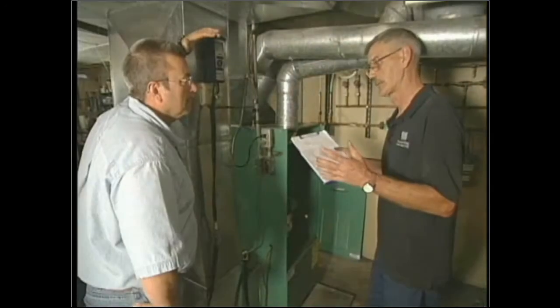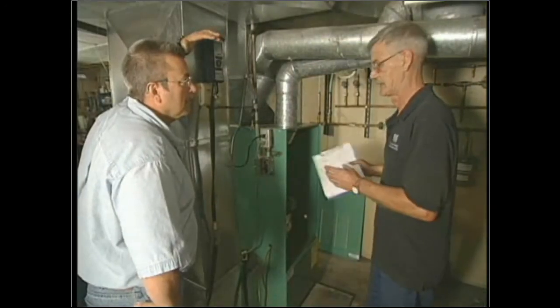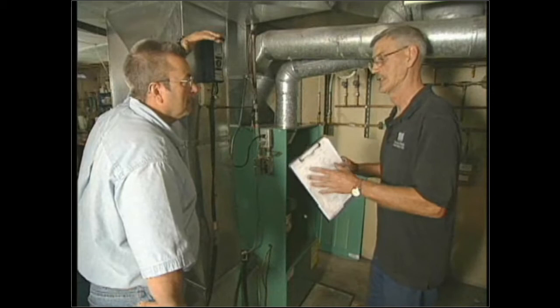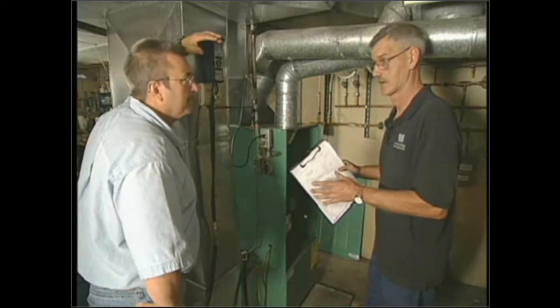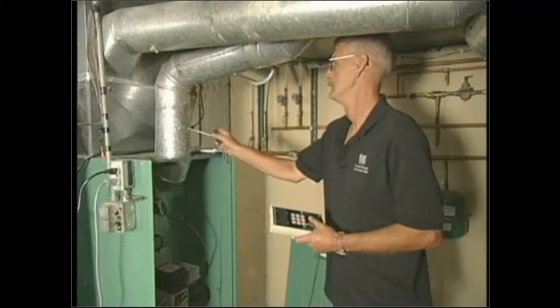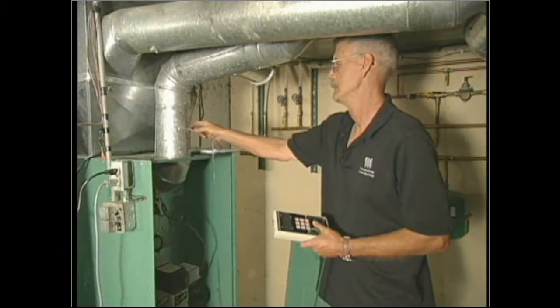If the pipe is too small, I can have spillage. If it's too large, then I don't get true draft if I'm measuring in the wrong spot. Okay. So I'll get it centered, then I'll take my reading, and that's all there is to a draft test.